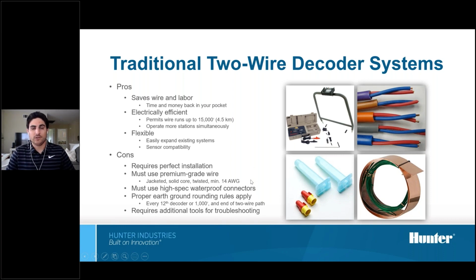So up front, there could be a little bit more or significantly more costs associated with a traditional two-wire decoder system. So sometimes we tend to see these types of projects on the higher spec commercial projects as opposed to lower end light commercial, mid commercial type projects. Last thing as well, in terms of troubleshooting, it can be a little bit dicey for a two-wire system, especially if you do have issues with your wiring connections or not proper earth grounding. You've got your wire trackers here, your ground fault locators, more costs associated with a traditional two-wire system. So that's kind of your give and take there.